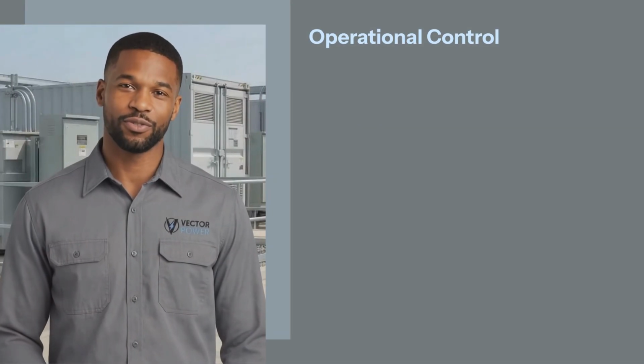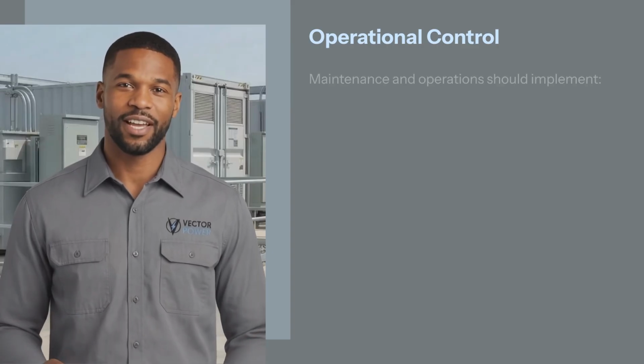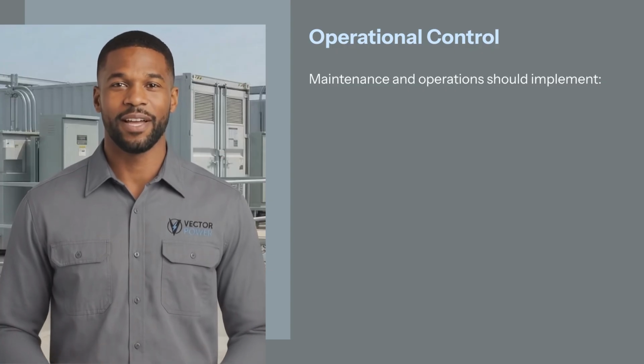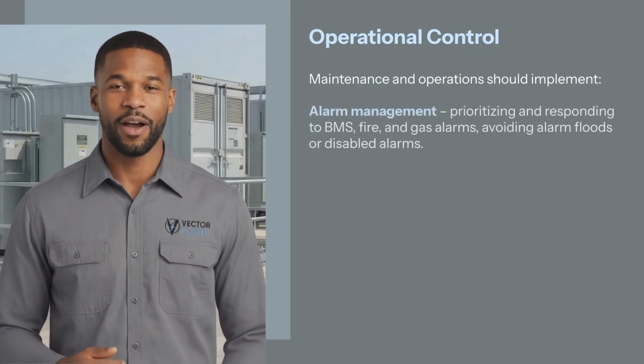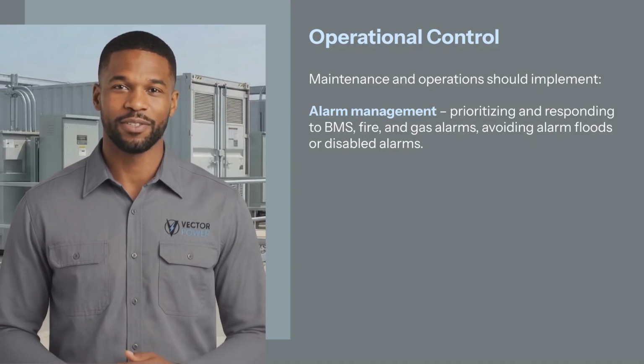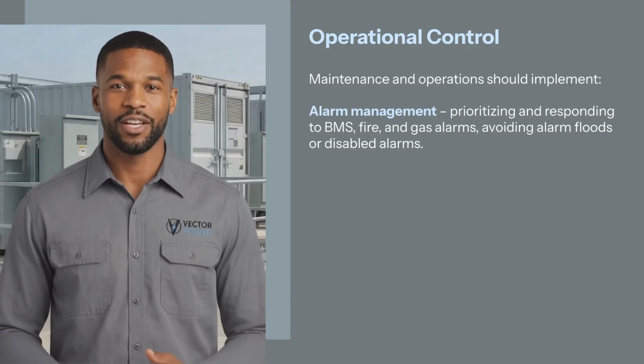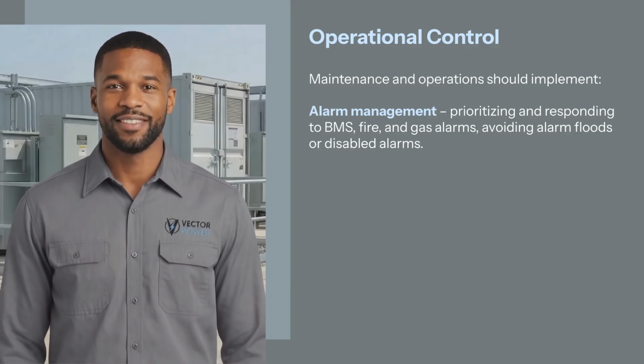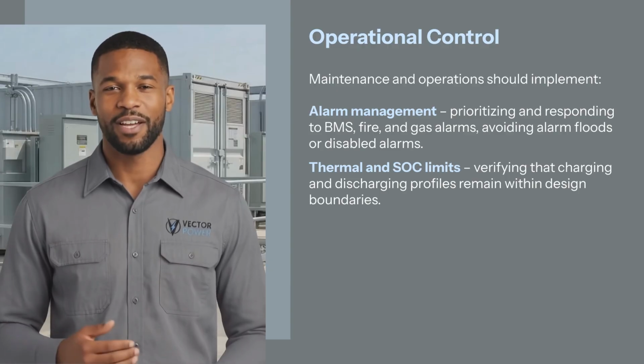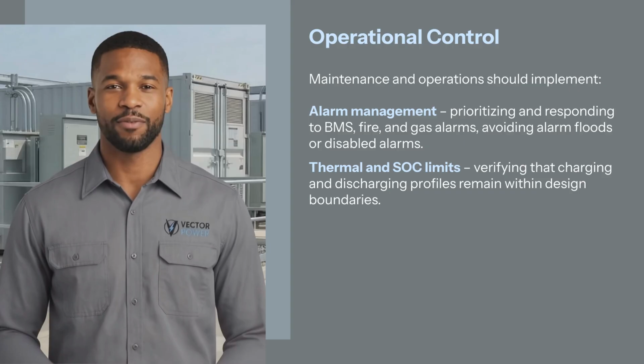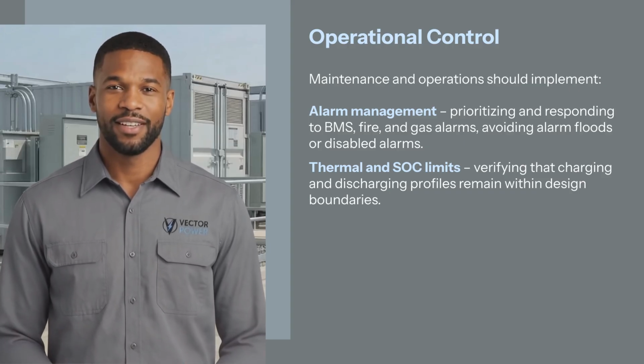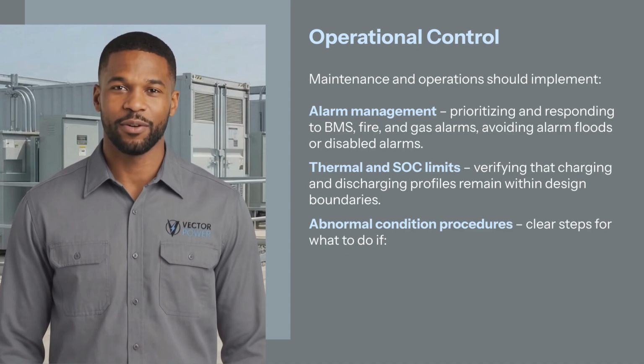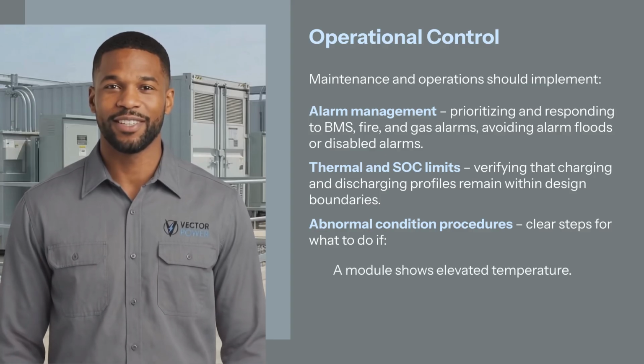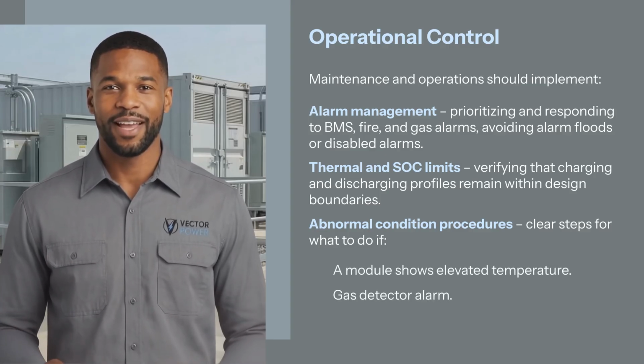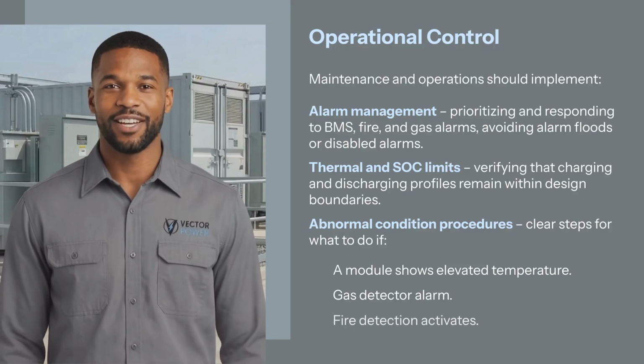Now let's look at operational controls. Maintenance and operations should implement alarm management, prioritizing and responding to battery management system, fire and gas alarms, avoiding alarm floods or disabled alarms; thermal and state of charge limits, verifying that charging and discharging profiles remain within design boundaries; and abnormal condition procedures. This includes clear steps for what to do if a module shows elevated temperature, a gas detector alarms, or the fire detection activates.